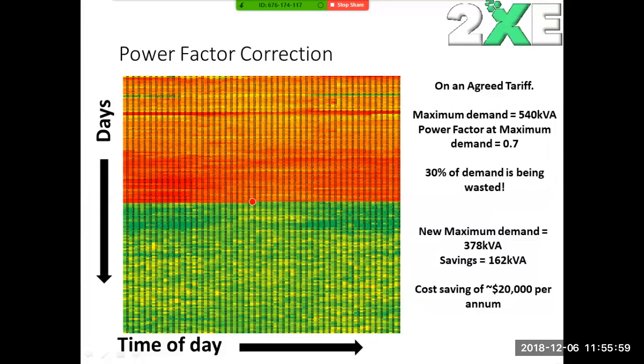So that's why it's turned to green now. Green means it's above 0.95, and that's a good value for your power factor. What that basically means is that you stop wasting 30% of that demand. So your new maximum demand in kVA is now 378.